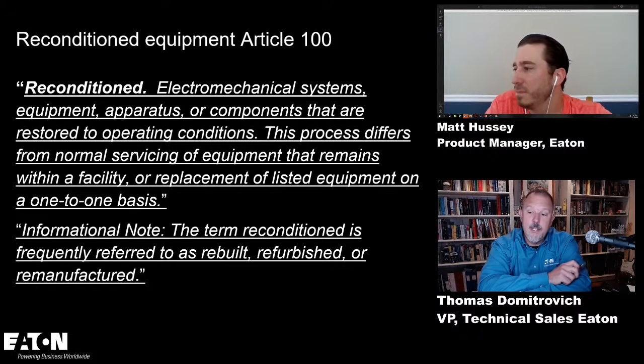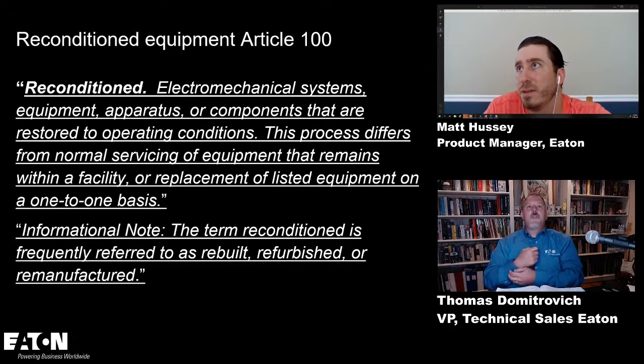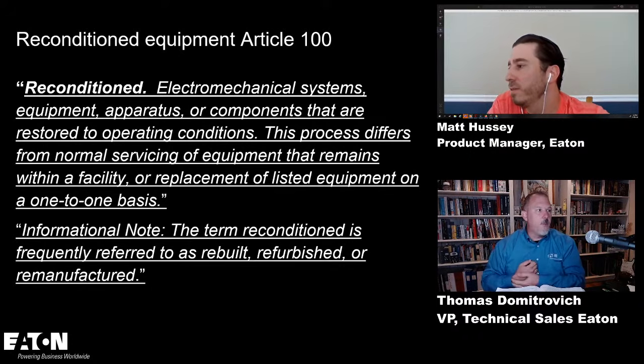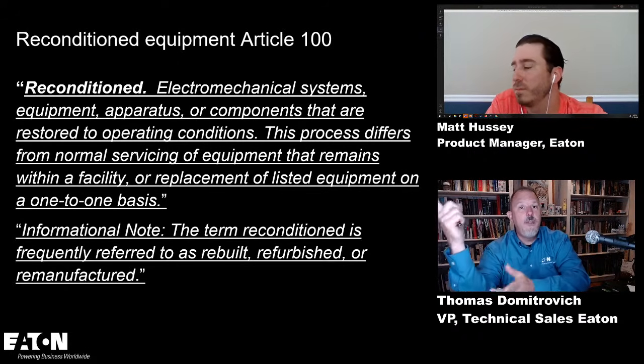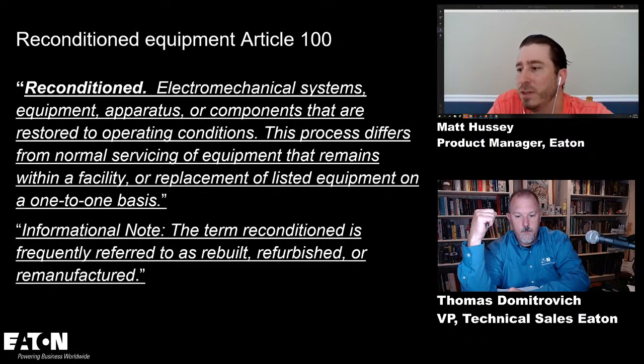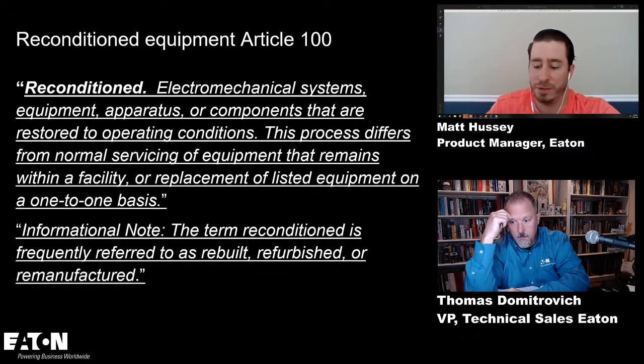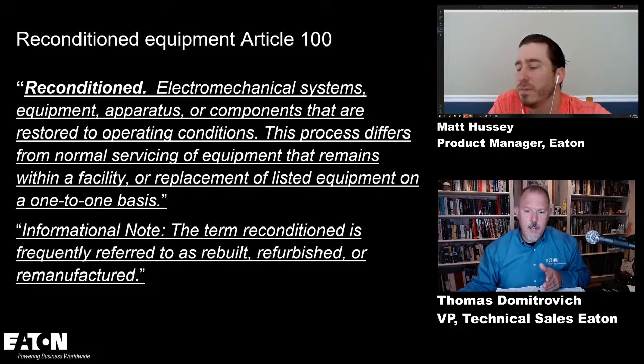Yep. Don Ganir asks, is replacing the vertical bus a repair? Well, it's obviously changing. That vertical section is listed. I don't believe it. What would constitute that being repaired? So if you would be replacing the vertical bus for a reason, I'm not sure why you would be replacing it, but for whatever reason you're replacing it. To your point earlier, you're questioning the integrity of the whole thing. We don't have manufacturer's instructions on how to do that in the field, right? Usually, if anything, there are buses designed to be added on to different sections or sections removed, but that's usually to replace it within a new section. Gotcha. All right. So you got the one for one.